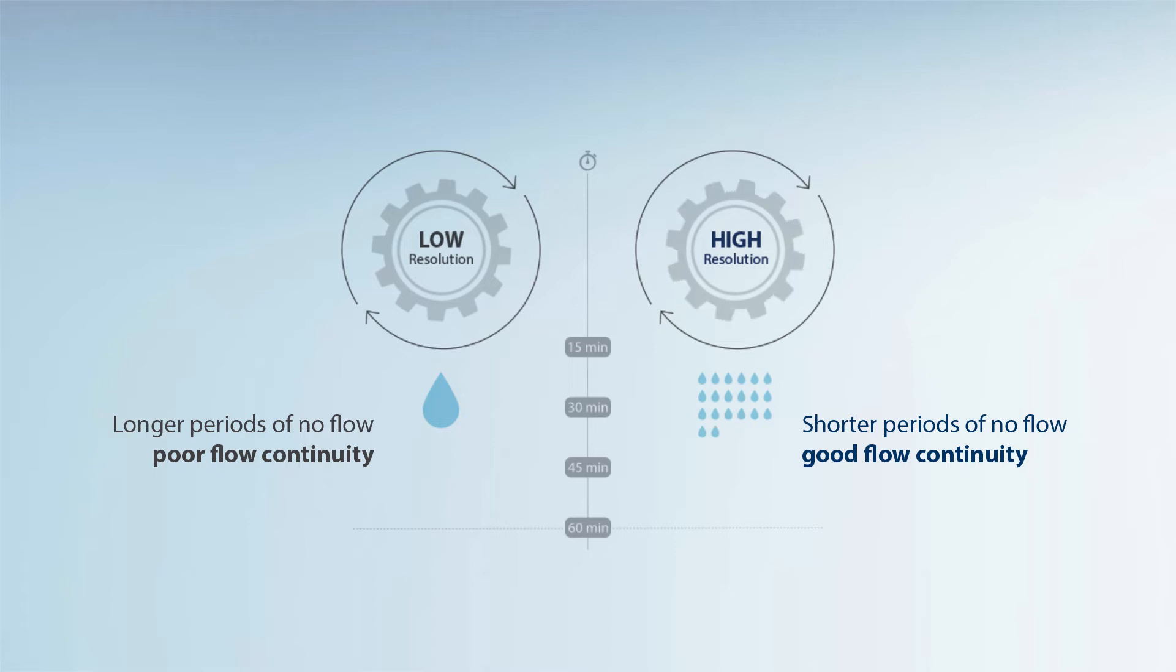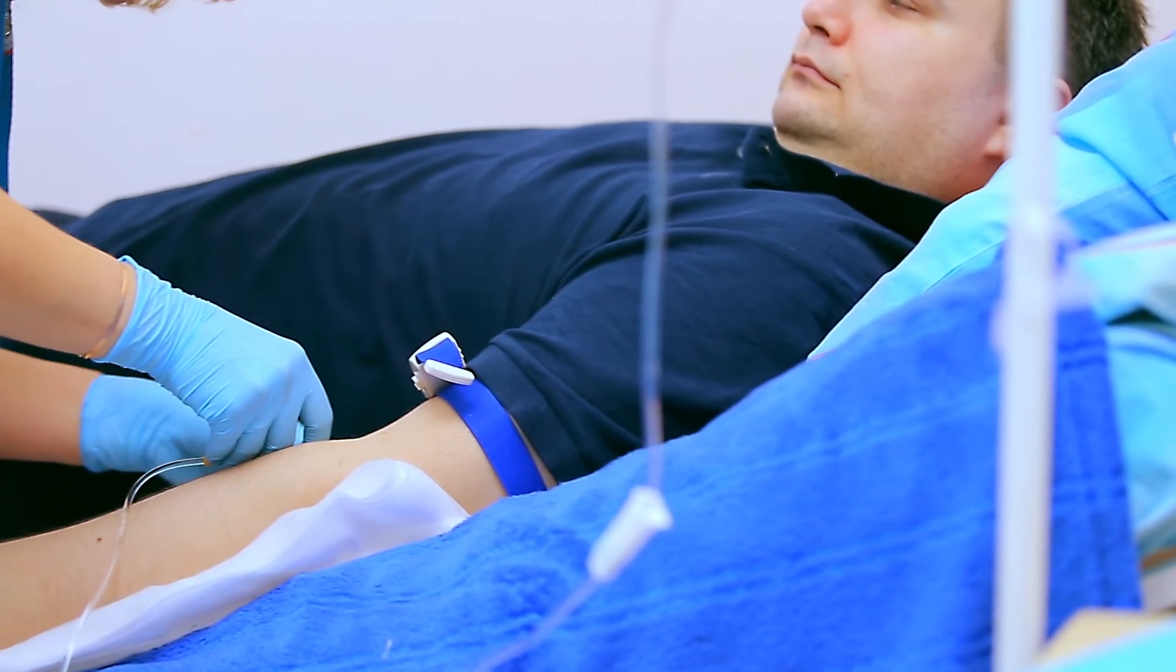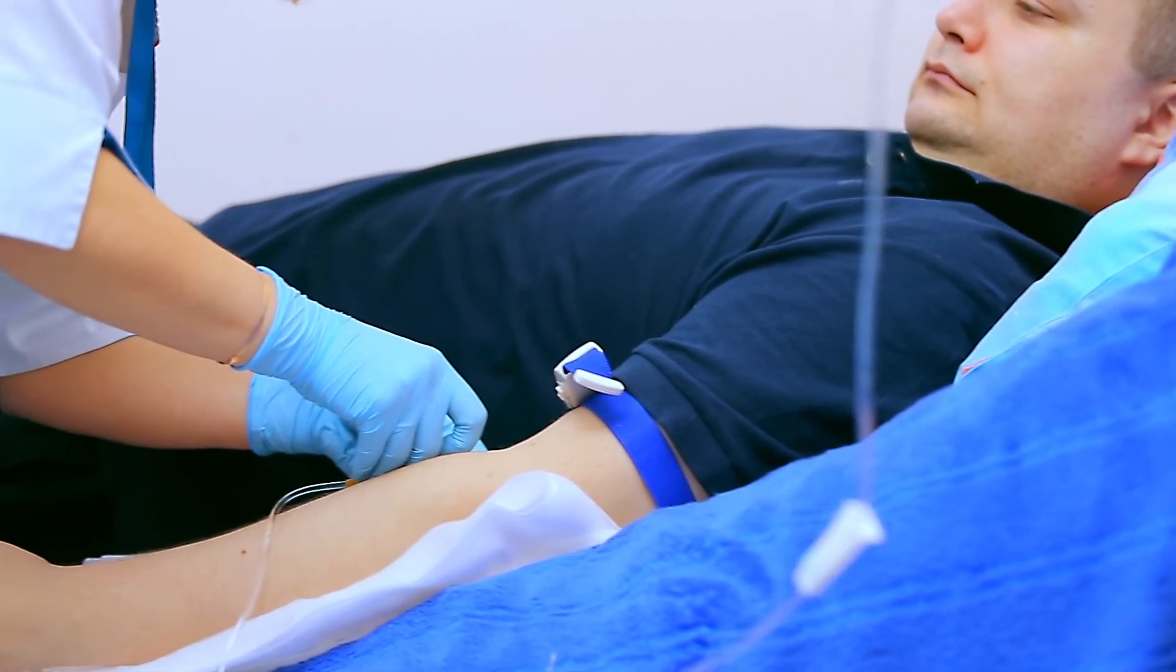Continuity of flow is not a big concern when the flow rate is fast, but it does become much more important with low flow rates, especially if the medication being infused has a short half-life.